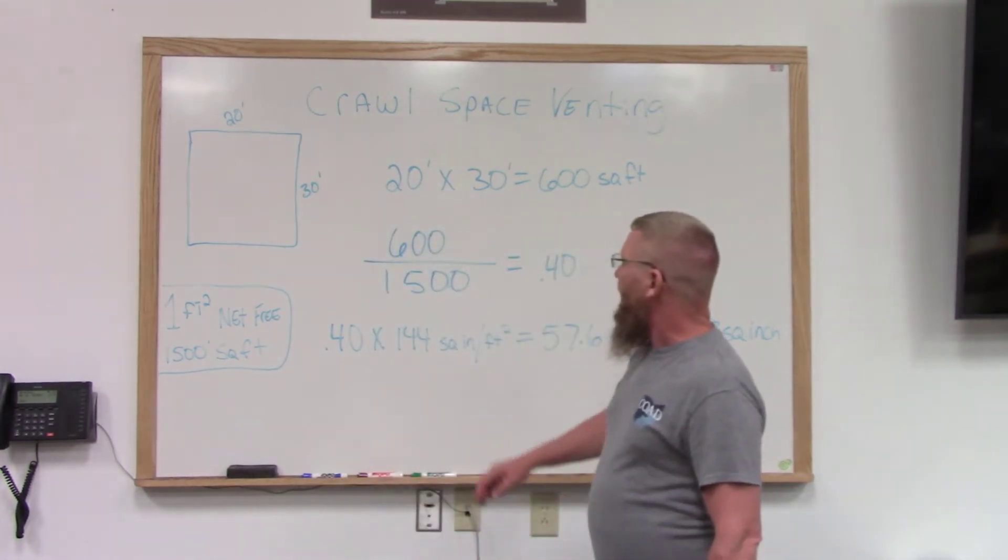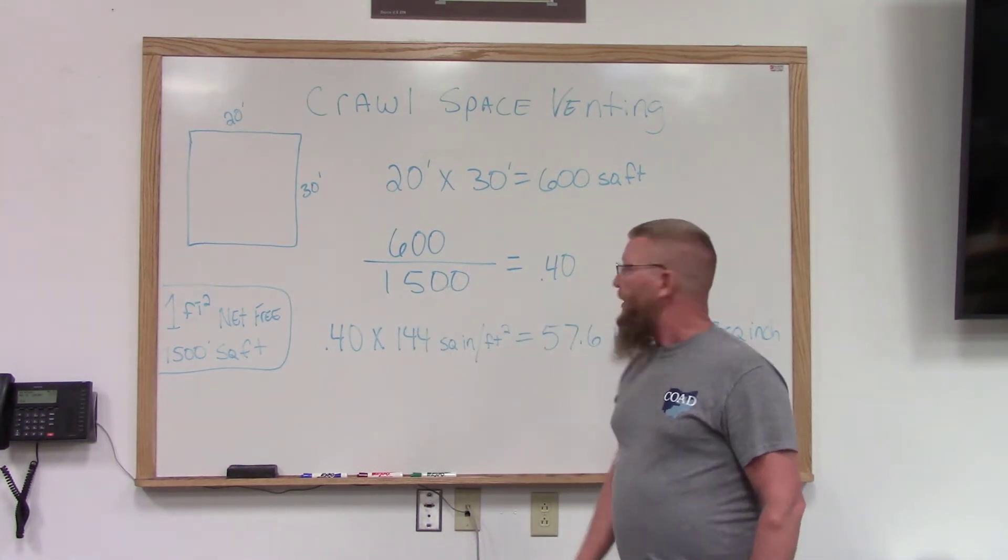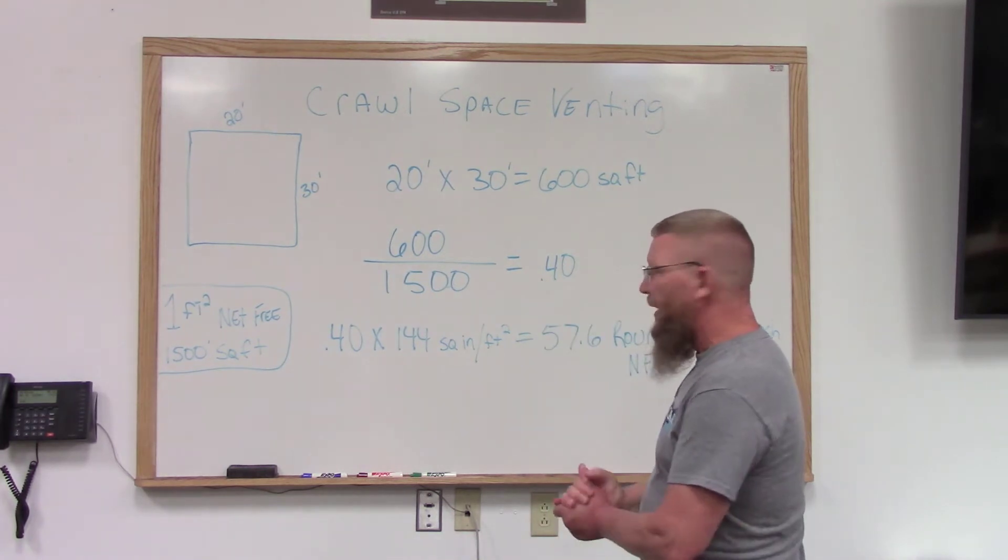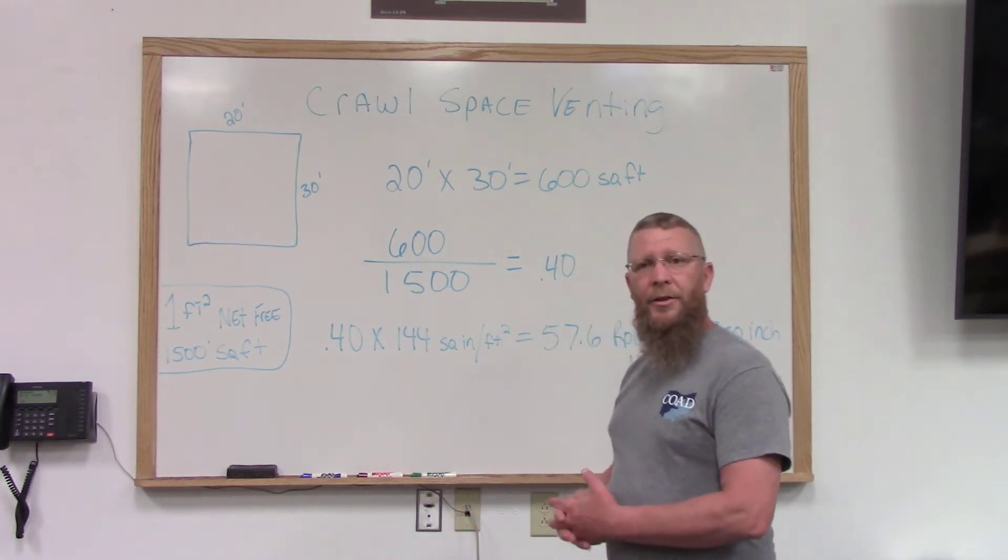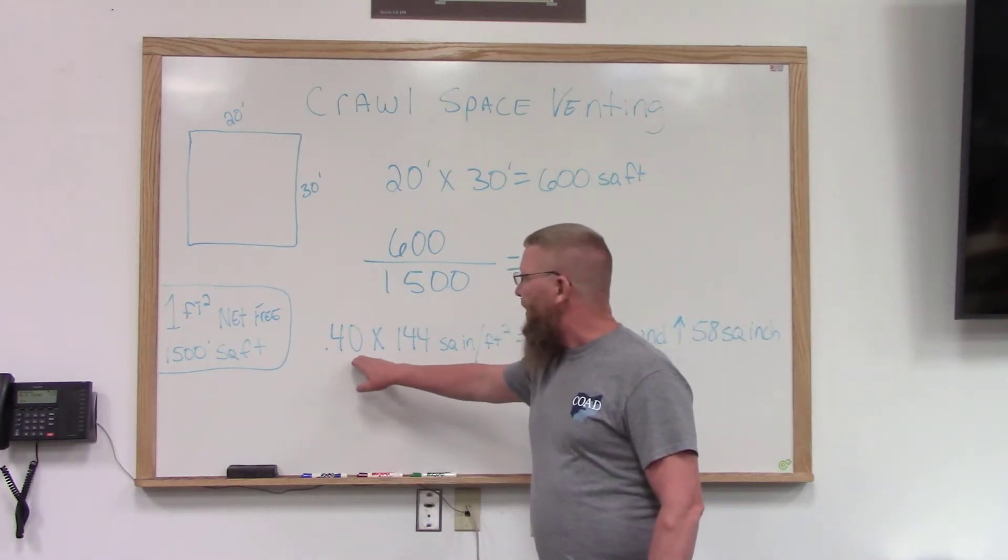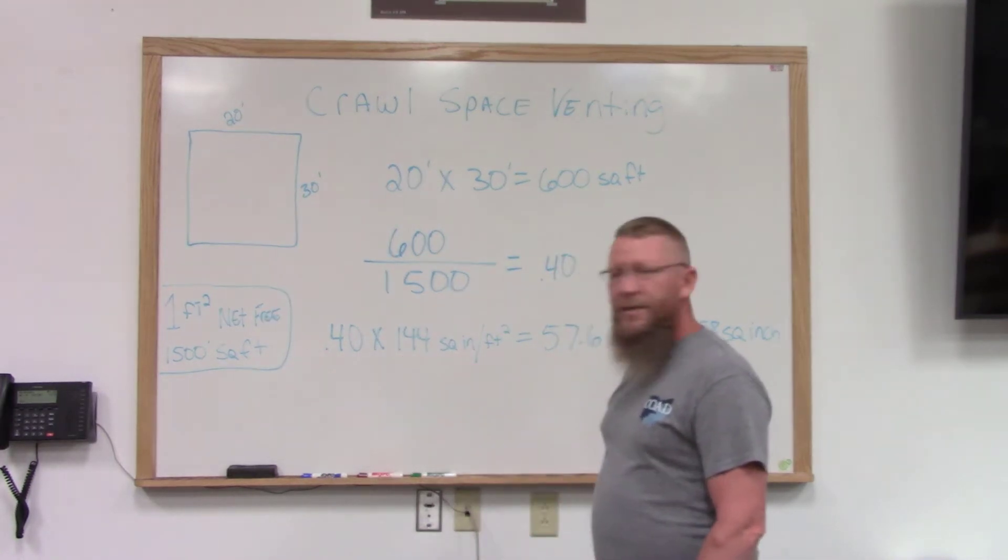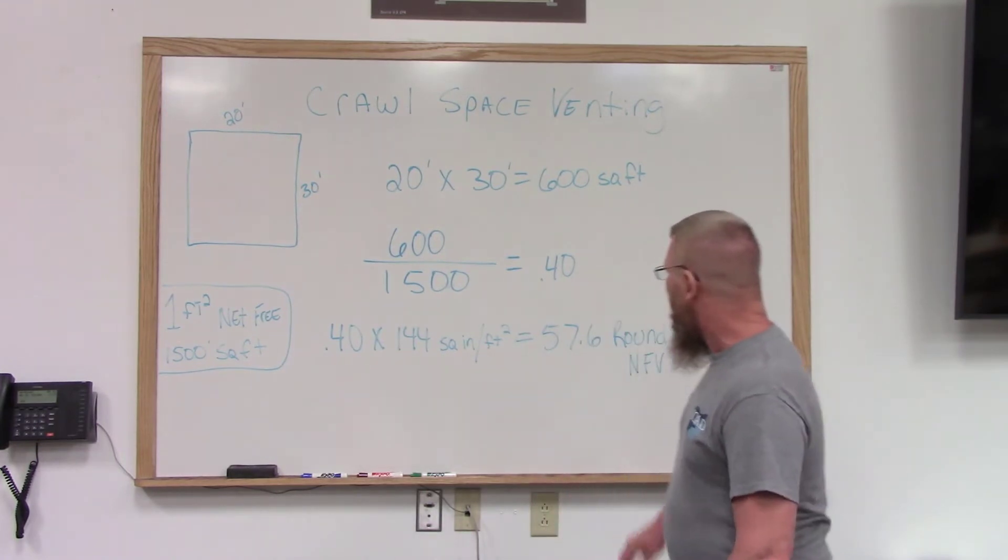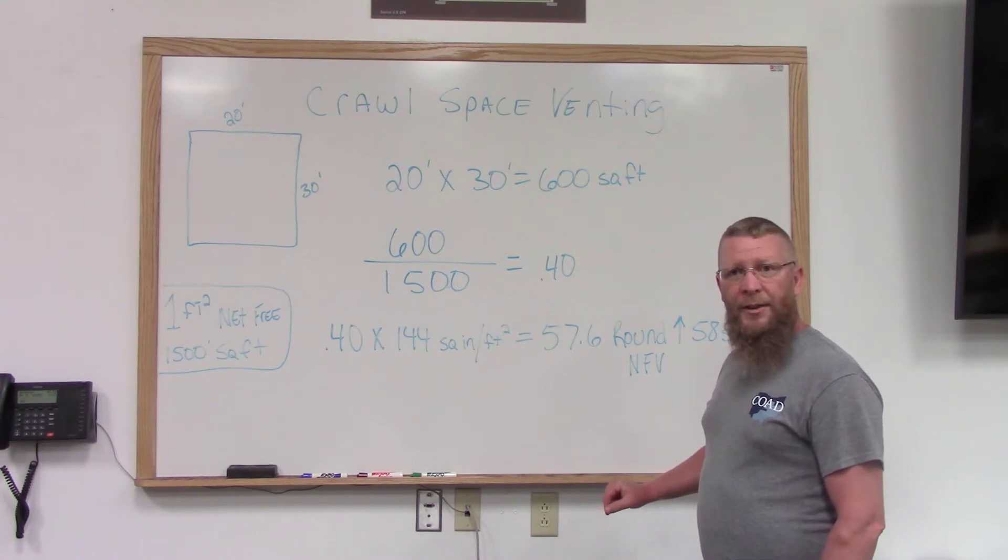So I'm going to take 600 and divide 1,500 into it. That comes out to 0.40. Well that's in feet, so I need to change that into inches. And how I'm going to do that is, I'm going to take my 0.40 and multiply that by 144, because that's how many square inches are in one square foot. That comes up to 57.6 square inches.